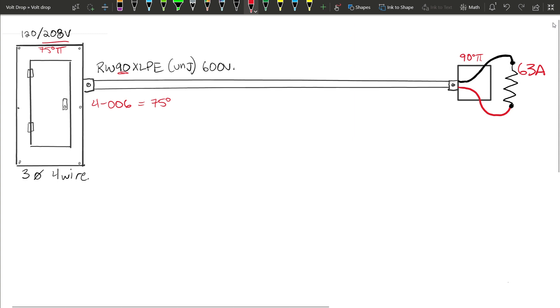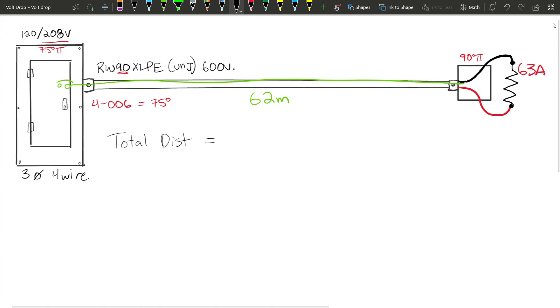We have 90 degree insulation temperature that'll come into play later when we look at the distance correction factor from the last video — we're going to apply it a little differently here. So we have a 63 amp load and we're going to determine what size conductor is required for a 62 meter distance. The total distance from the overcurrent device all the way out is 62 meters.